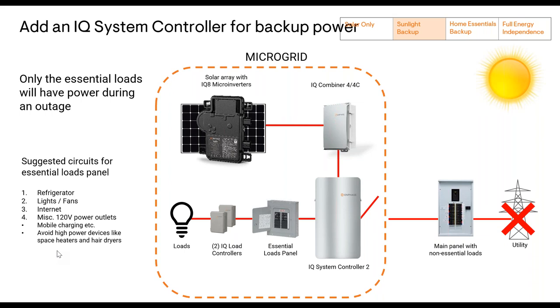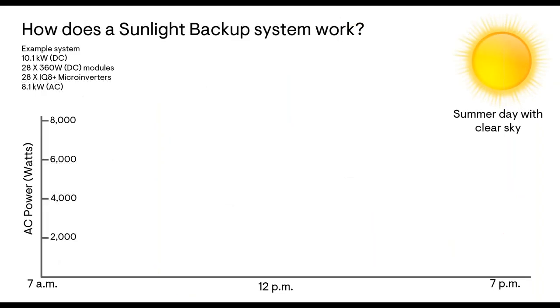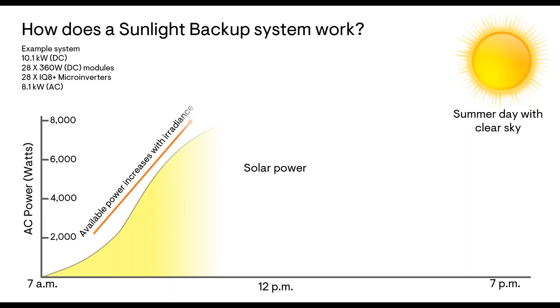And when you're sizing backup, it should be a conversation - what does a homeowner want to back up? But if they're choosing sunlight backup, you really want to make sure that you're using lower power loads. The reason is because you want to make sure that you have a pretty wide time frame throughout the day where you're likely going to have enough power to power those loads.